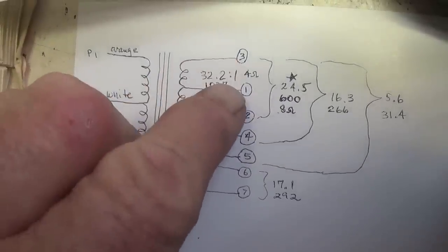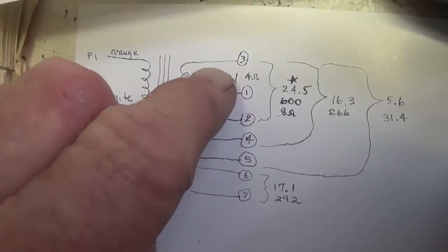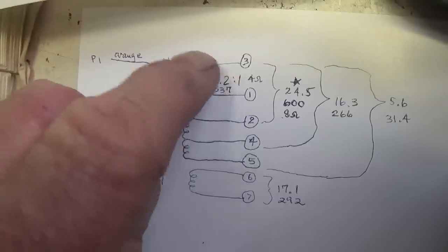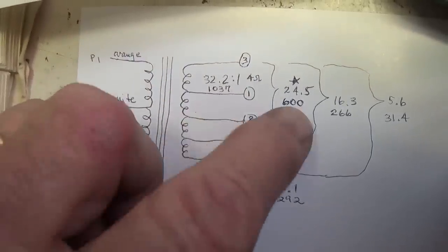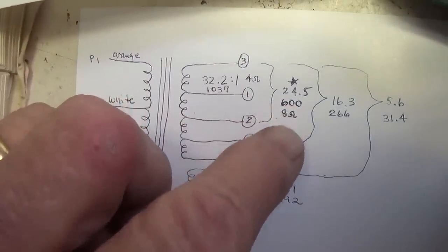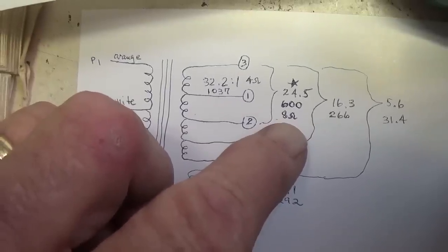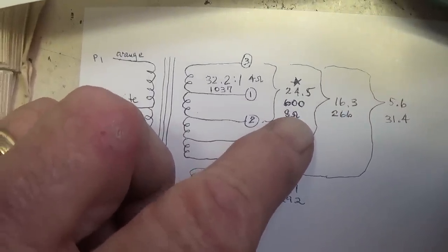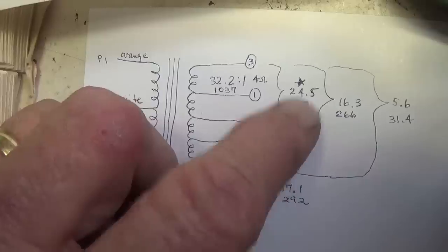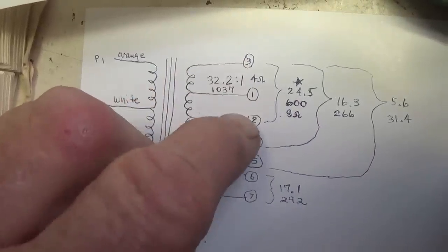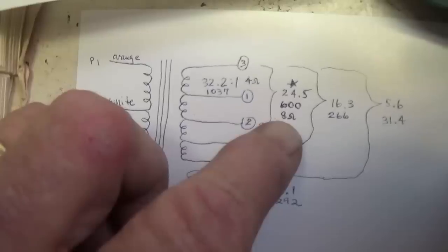So 3,1 is going to be the 4 ohm output. Between 3 and 2, I got 600. If you multiply that times 8 ohms, you're at 4,800, which is right in the proper range. So 3,2 will be the 8 ohm output.